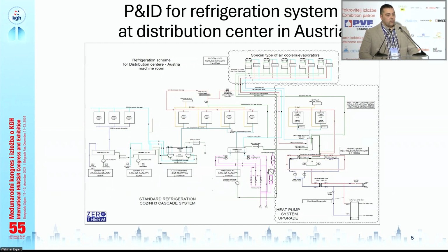And right above the buffer tank, we installed the measuring unit with flow meters and temperature transmitters, and that way we were able to monitor the complete system and the real heat energy that we deliver to the heating system.